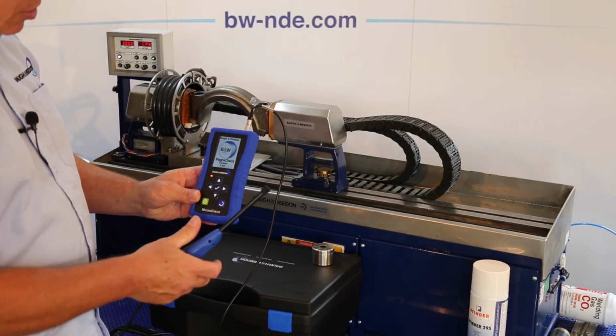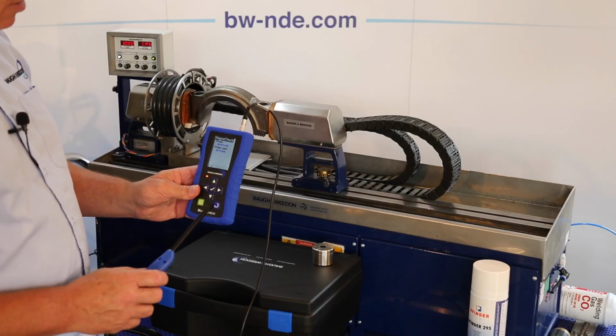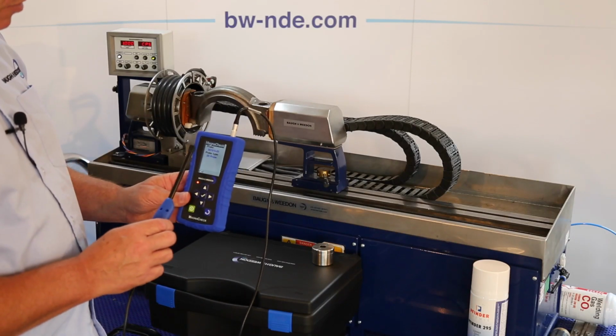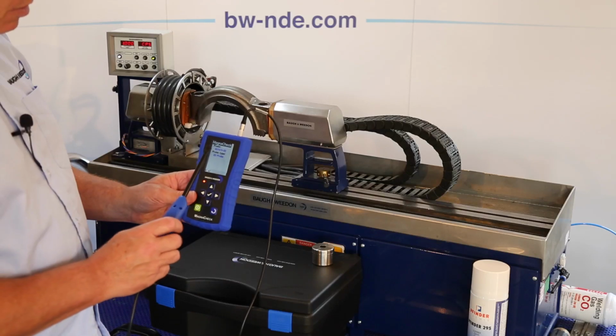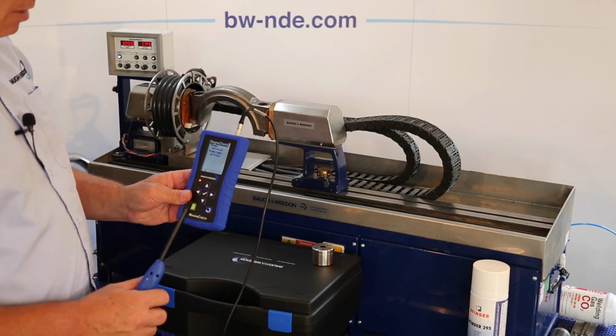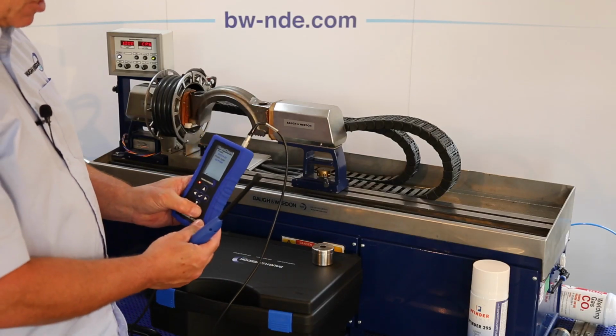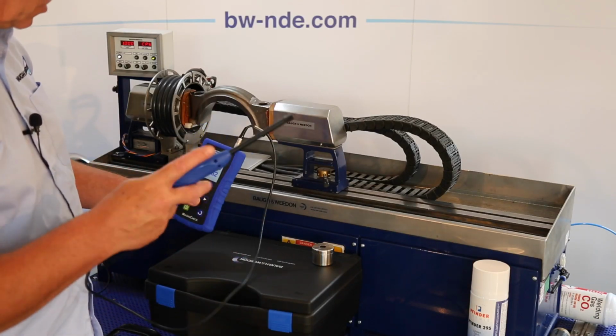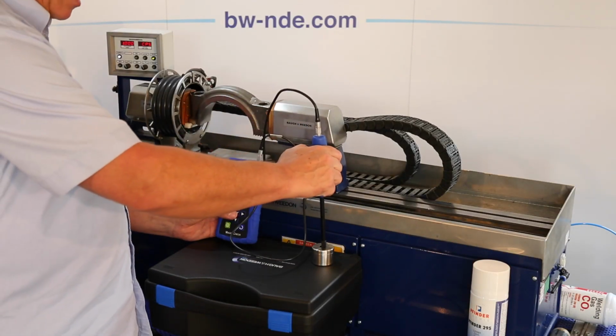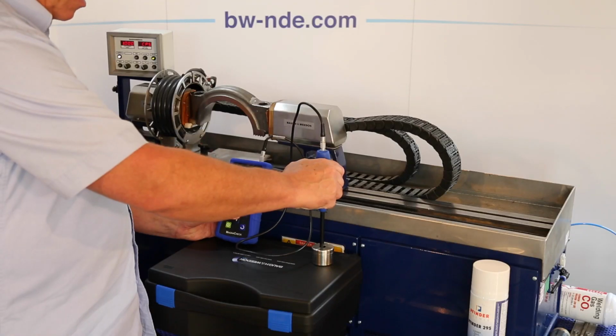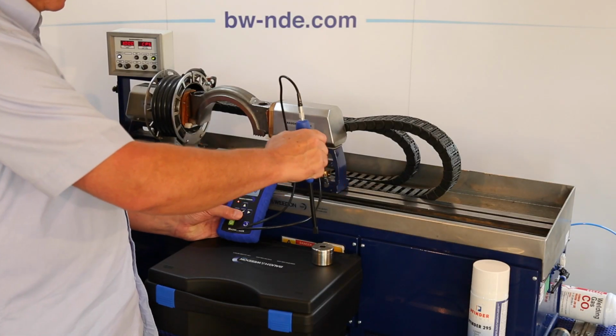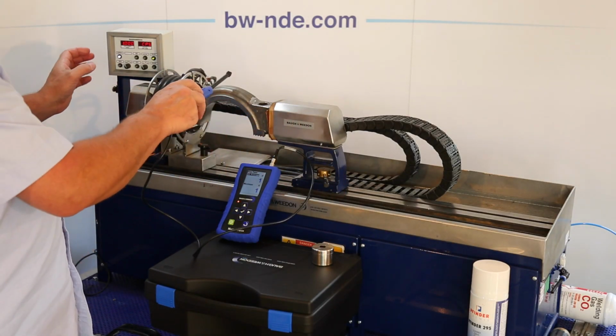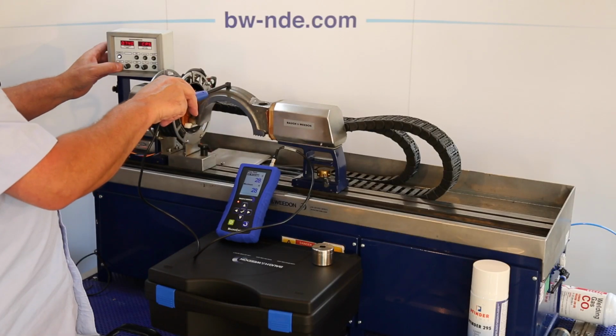To power on, press the green button. You'll get the Baugh and Weedon logo, followed by a screen with the probe auto recognition, serial number and what type of probe it is. Press the back button to start measuring. Place the probe tip in the nulling pot and press the tick to zero. Then you're ready to start measuring.